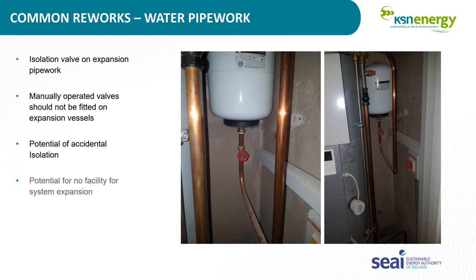What we would say is if you could fit a lock shield valve, something you have to use a tool for, to isolate the expansion vessel. That's what we would recommend, or better still, nothing at all. But if someone does decide to put something on, that it can't be accidentally turned off.